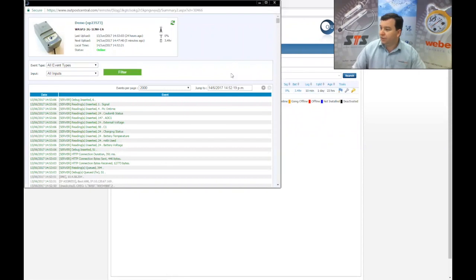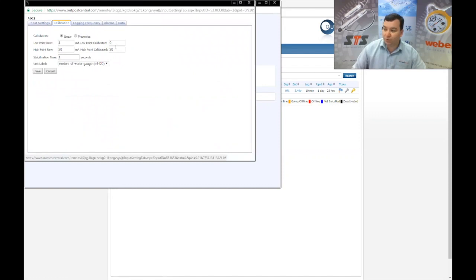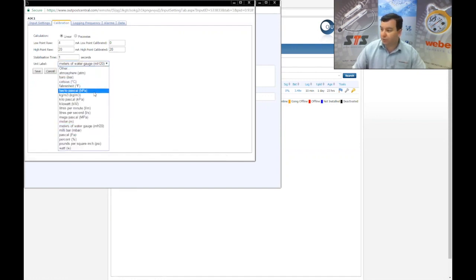You can have a look at any events that have been happening. You can also set up the 4 to 20 milliamp or whatever input it happens to be — calibrate it. We've got it set up at the moment as 4 to 20 milliamp, 20 meters, water gauge H2O. But there are lots of different options: Celsius, bar, meters, Pascals, watts — whatever you want to feed into there, you can get that calibrated however you'd like to see it.